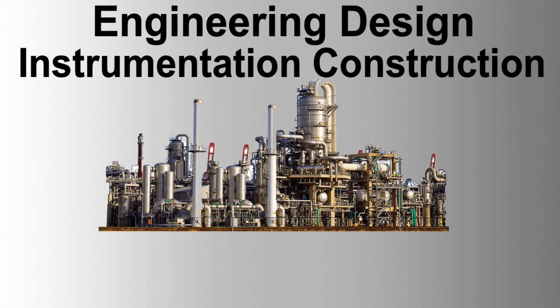Where practical, instruments shall be mounted on 2-inch NB pipe stands at 1.3 meters to CL of instrument above grade or platform. CL equals center line. All brackets and supports shall be protected against corrosion, e.g. by adequate priming and painting. Care shall be taken to ensure that any forces developed by the expansion of piping or vessels will not affect the instrument installation. A permanent label engraved with the instrument details shall be fixed at the location of each instrument.